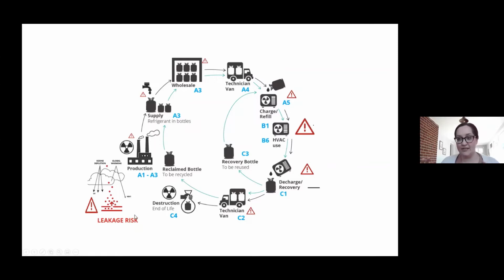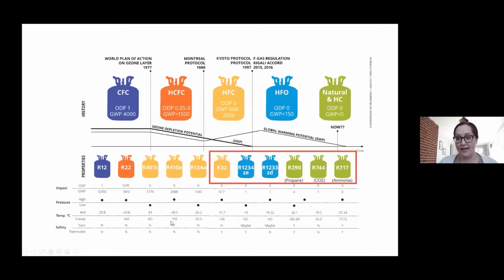The leakage risk is the most, I guess, meaningful impact here. So the A1 to A3 phase for refrigerant is very, very small in comparison to the amount that actually escapes to atmosphere, which contributes to global warming potential. So that's what we'll be talking about in terms of calculating refrigerant risk. But just to give everyone an idea, commonly utilized refrigerants are R410A. Very common that that's utilized.